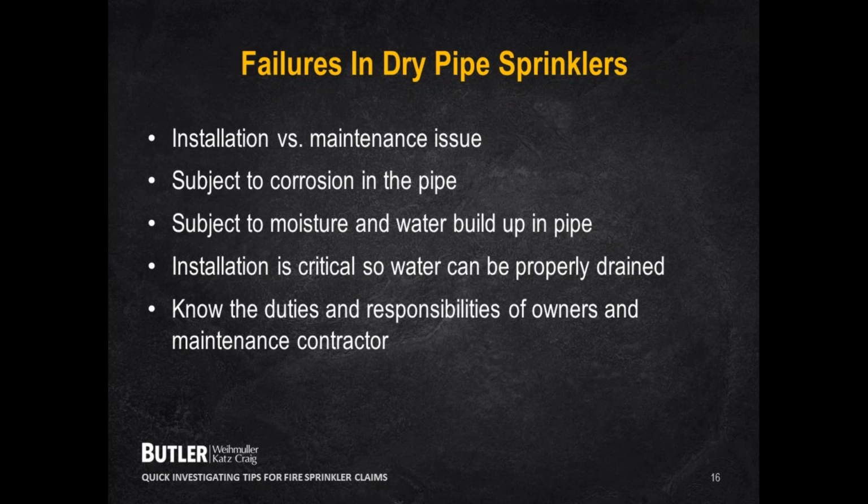If the insured doesn't have them, you may be able to get them directly from the service maintenance contractors. And sometimes over a period of years, as you know, there could be various service maintenance contractors as well. A lot of the contracts that we see for the service contractors, because they do the testing and the inspection, will specifically exclude, and I'm using finger quotes, the maintenance. And the maintenance of a system falls on the responsibility of the owner of the system. That has to do with draining the system on a regular basis.